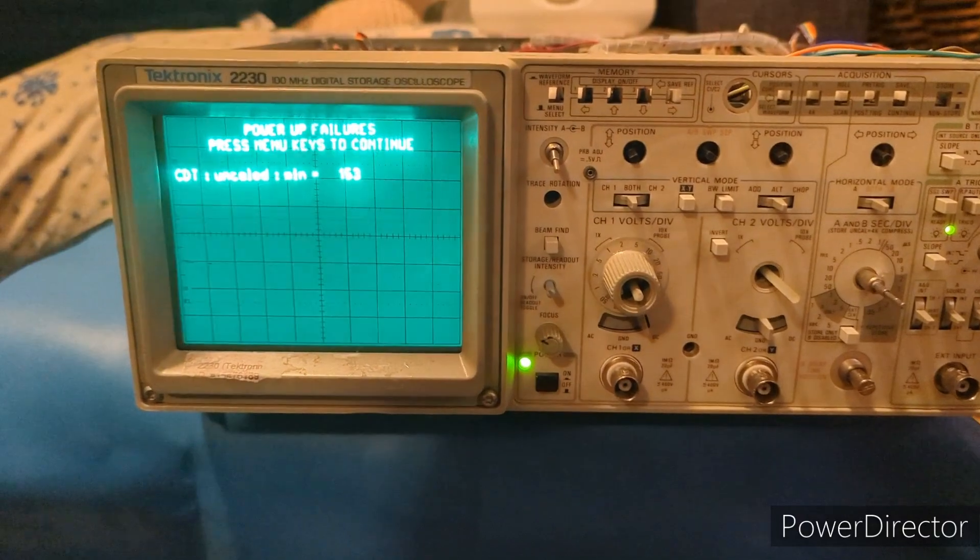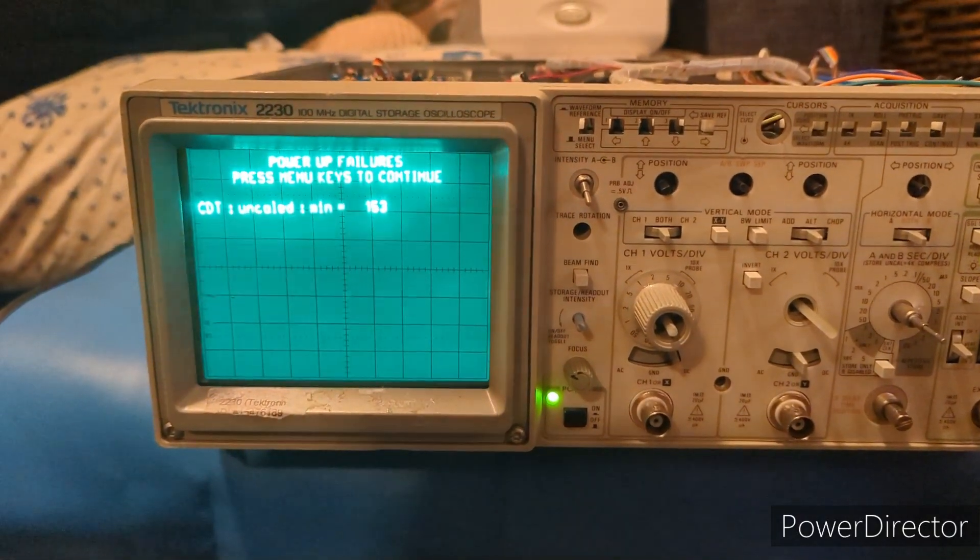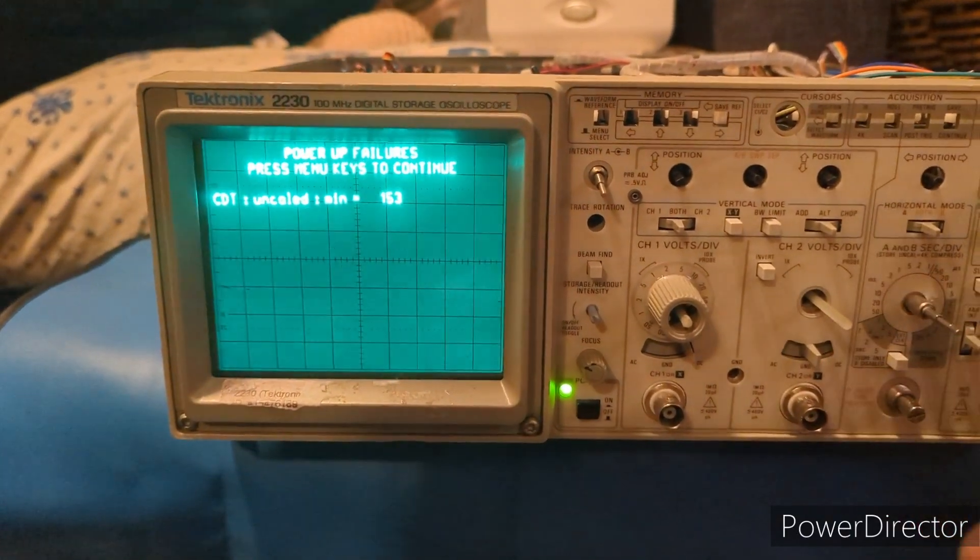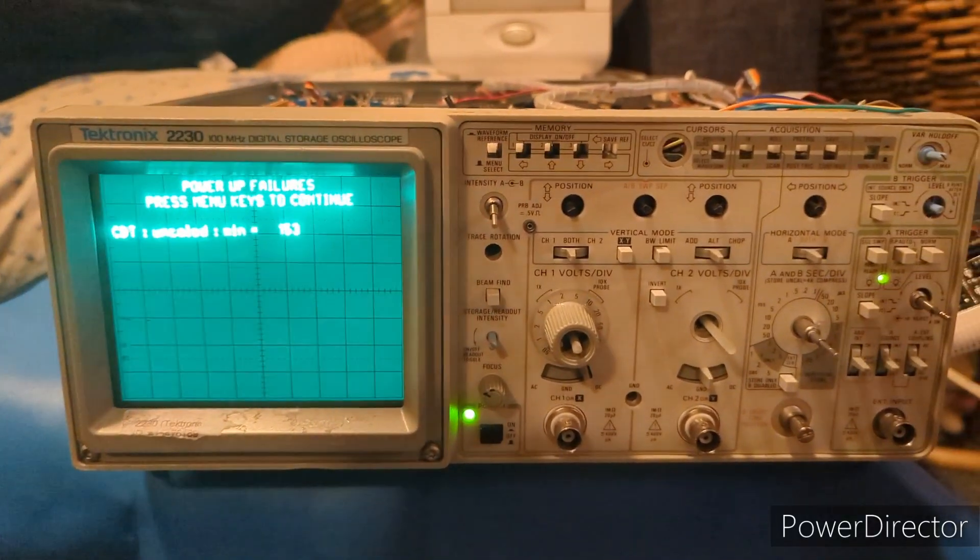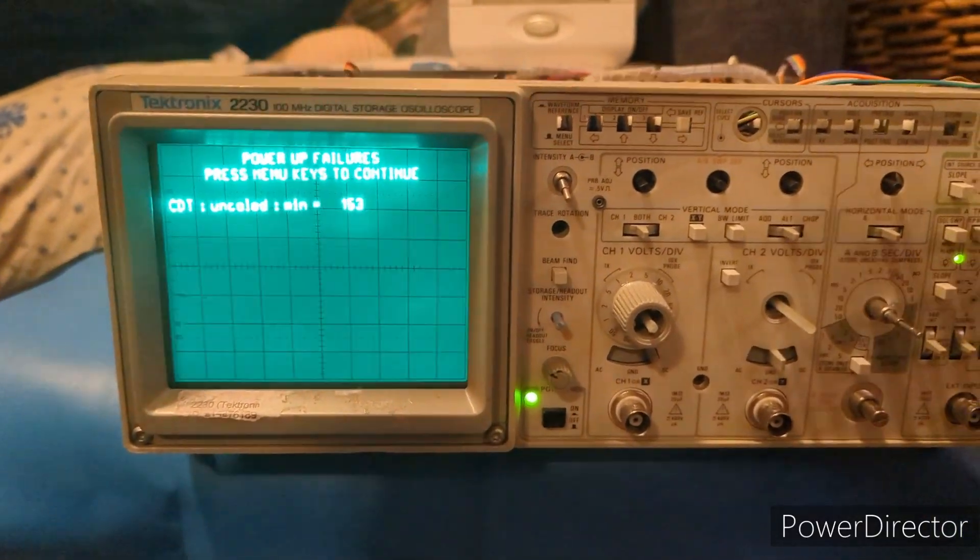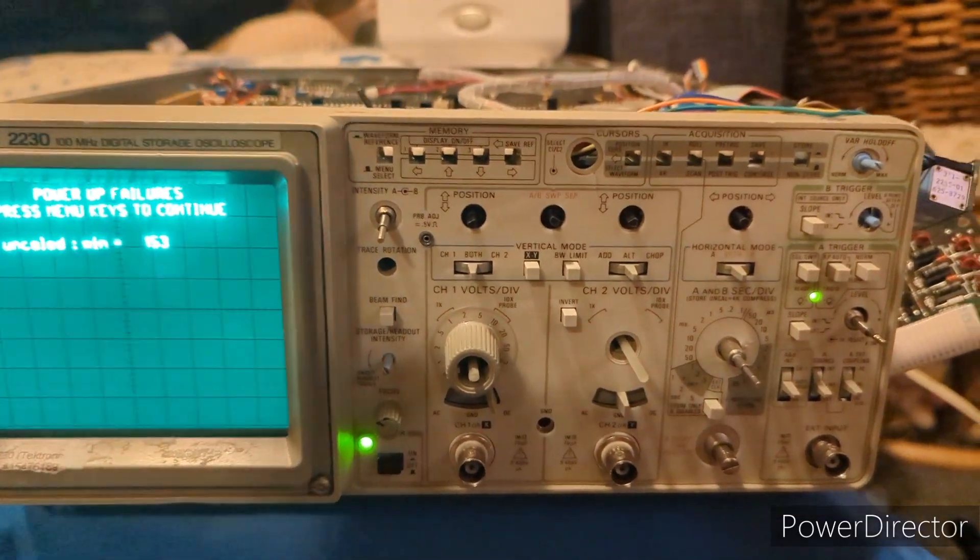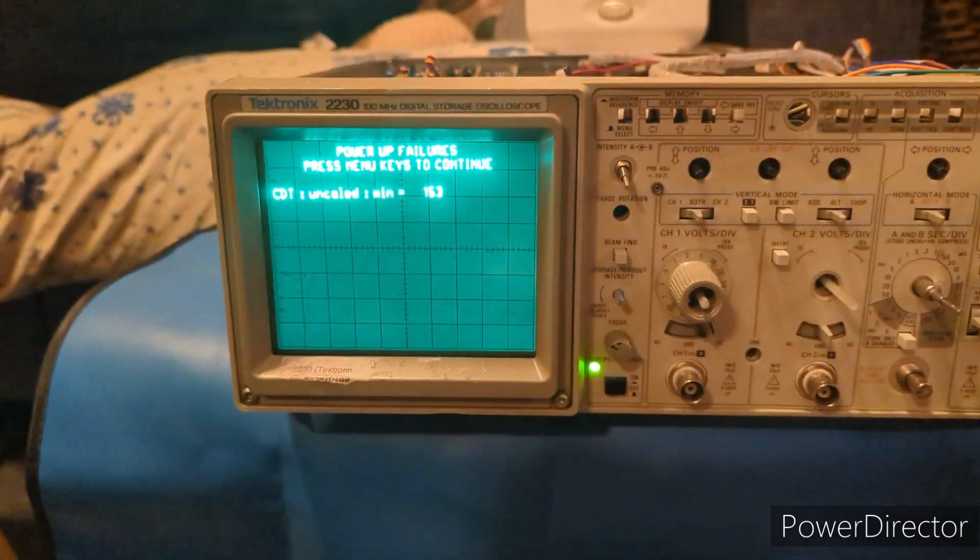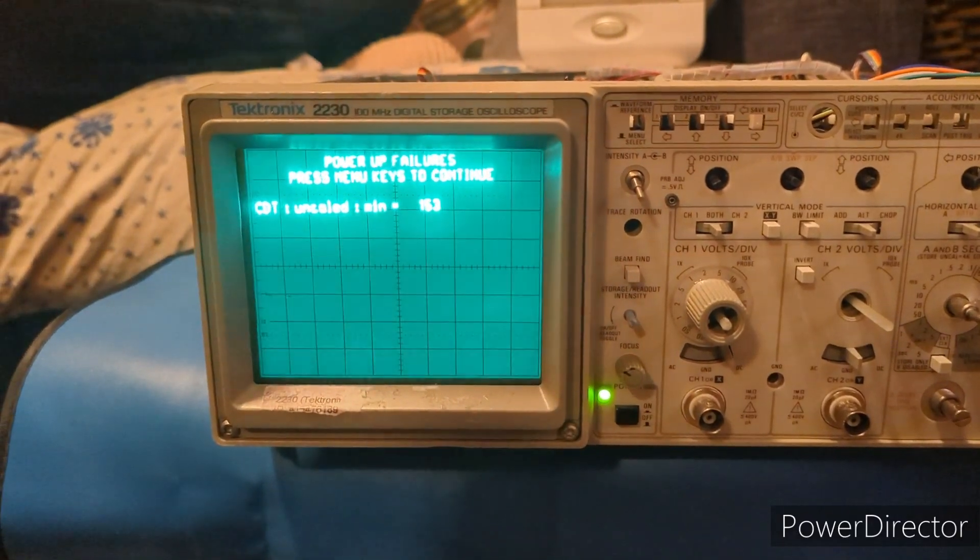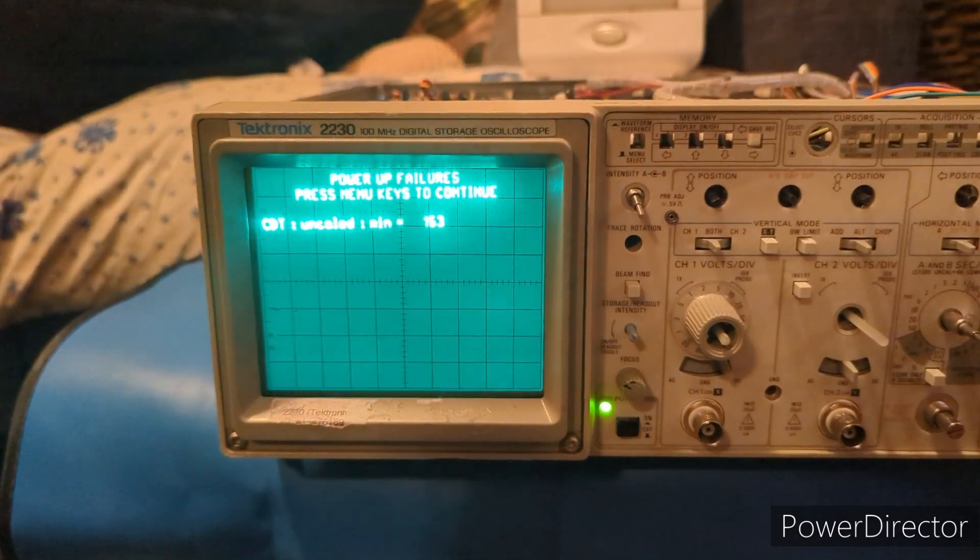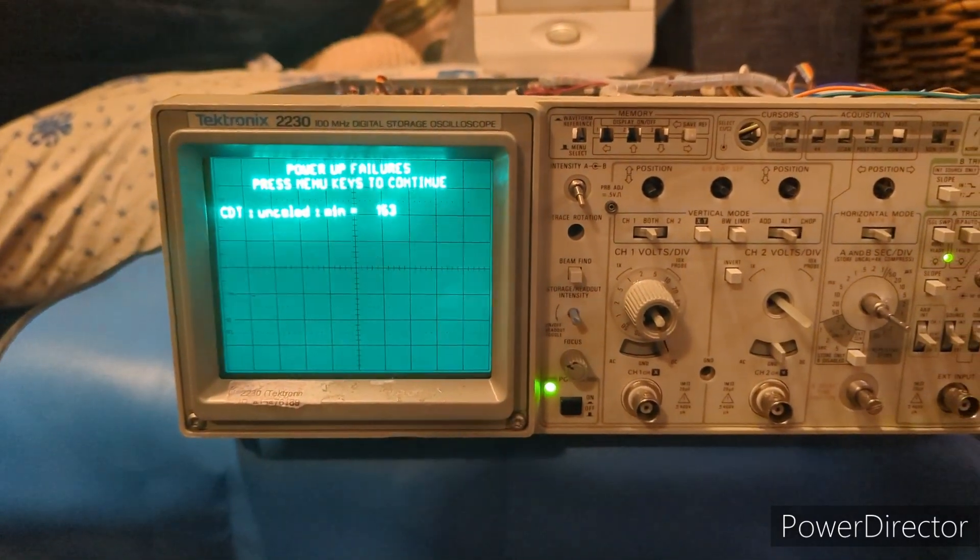None of the buttons would respond. The only buttons that would work normally were the readout intensity, the focus knob, beam find, and horizontal positioning. You could move the crosshairs back and forth, but that was it. None of the digital keys, pressing the menu, the memory keys, any of the acquisition buttons - nothing would make these squares go away. So I decided to isolate the analog circuitry from the digital and start working on that, and that was part two.